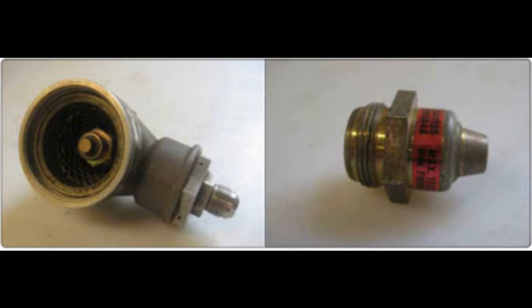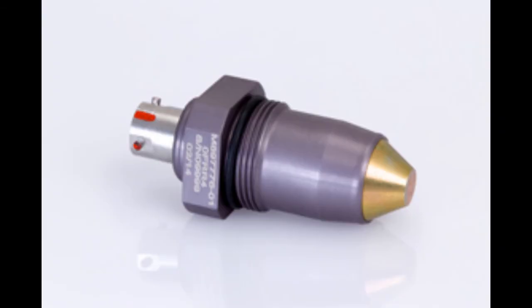The total life of the squib starts on the day the cartridge is made, and you must replace it at a specific time. This includes any shelf time. So the total life starts from the date of manufacture and includes any shelf time. Service life is a little bit different. Some manufacturers require a reduced life starting from the date the cartridge is installed in the cylinder. So that's just the time that the cartridge is in service.